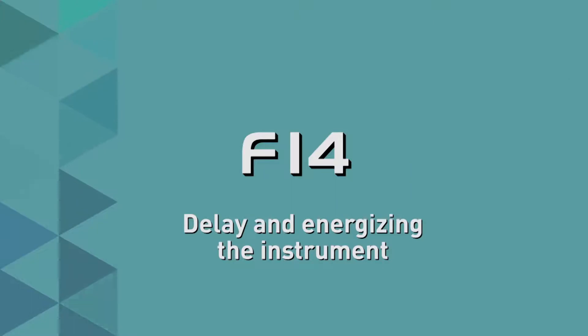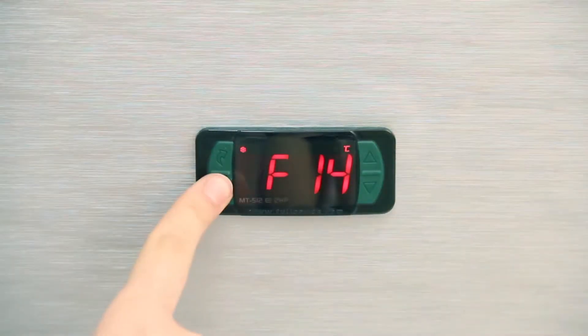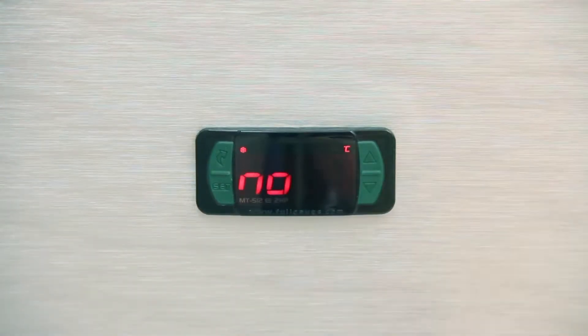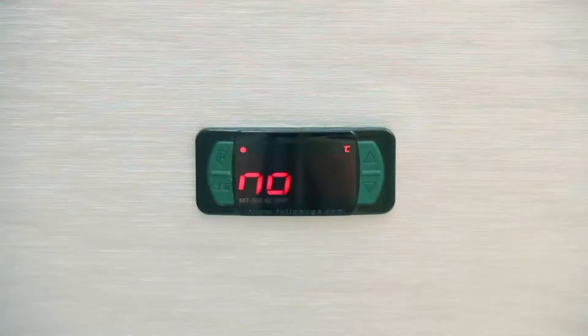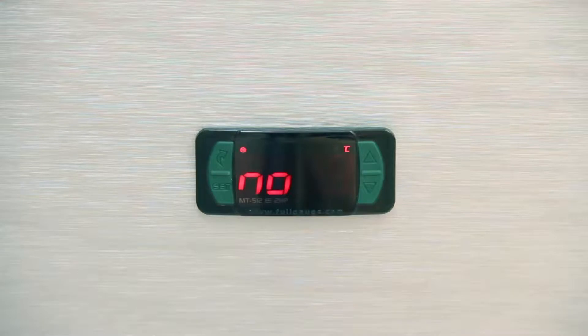F14 Delay in Energizing the Instrument: This setting prevents the generation of electricity demand peaks in the event of failure and return, when there are multiple devices. Select No so as not to delay the energizing. If you choose a delay, provide a time of 1 to 240 minutes. In the examples, we chose not to adopt the delay.